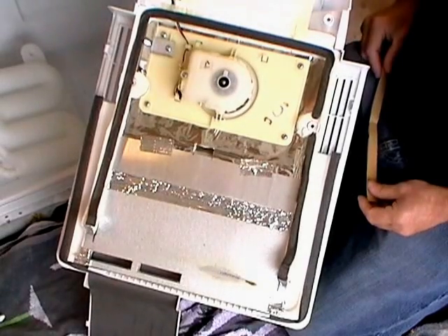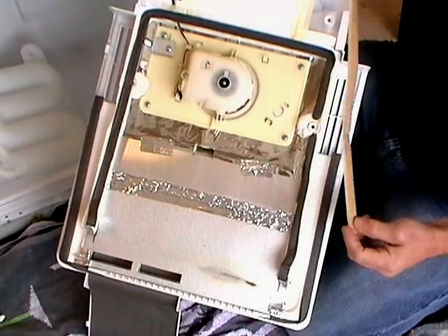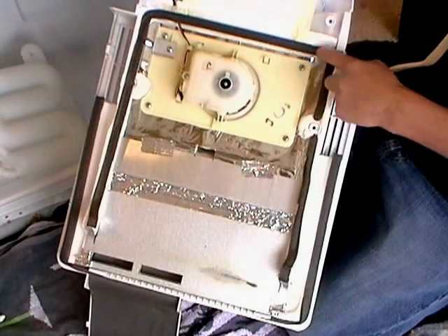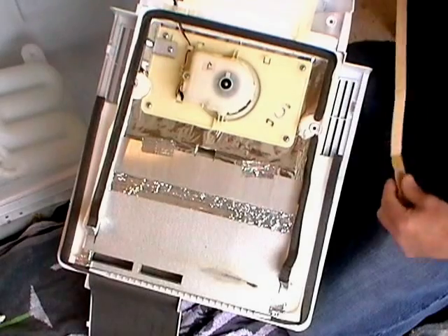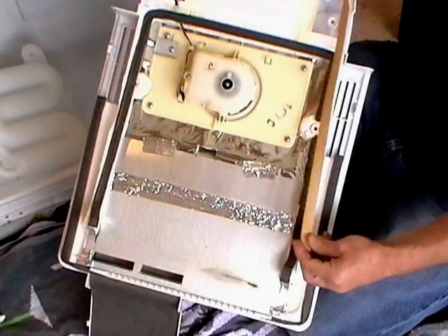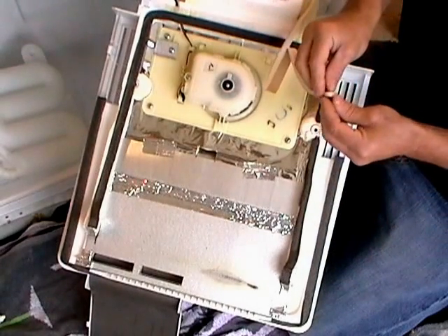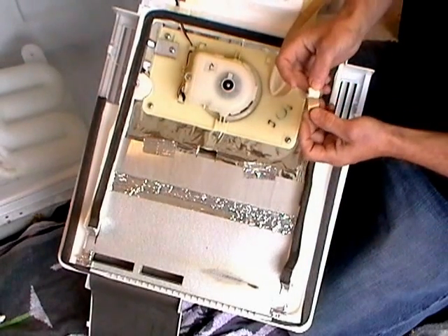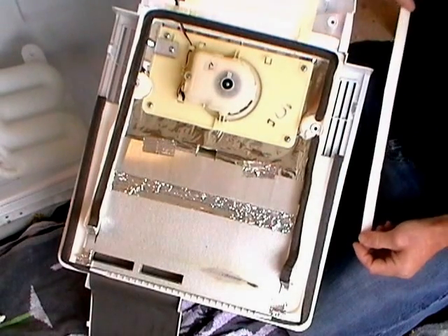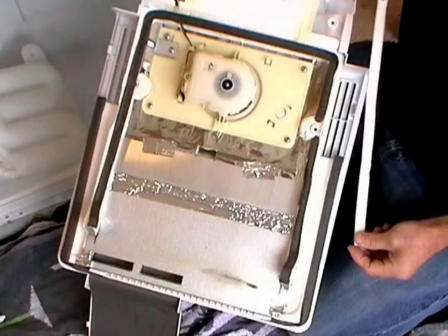Part of the modification is that when you've fitted the new sensor the original problem of icing damages the foam on one side of the panel. Part of the kit is some self-adhesive foam and you can repair the damage to the back panel. You've still got the problem of ingress of moisture into the polystyrene bits, so if the back panel is shot then no repair is possible.